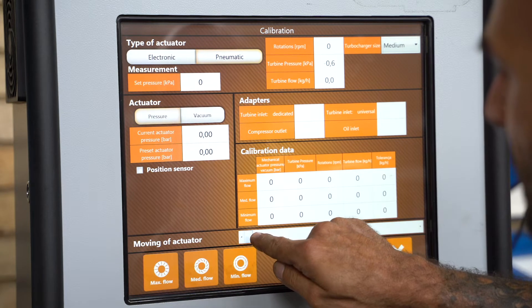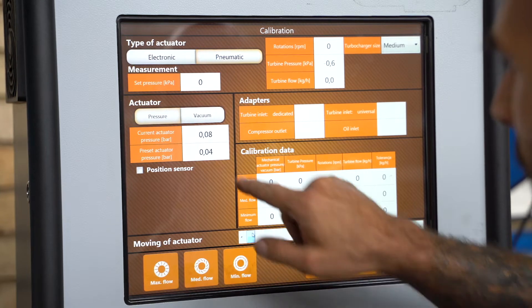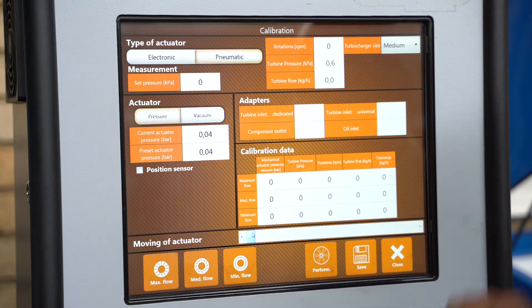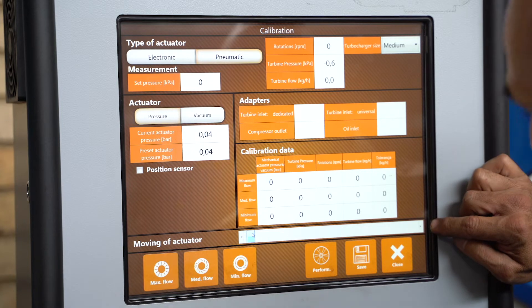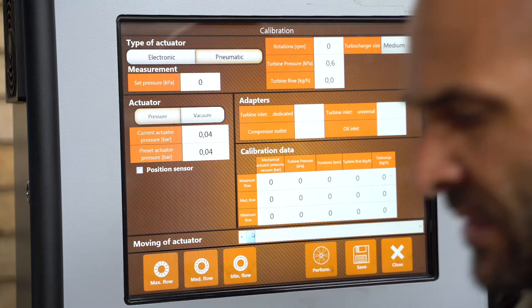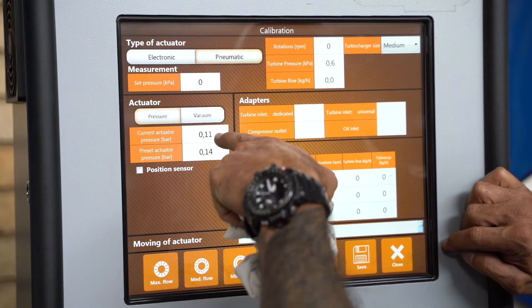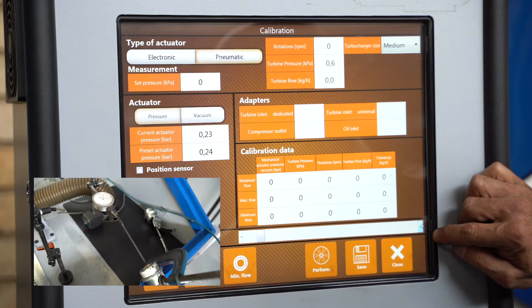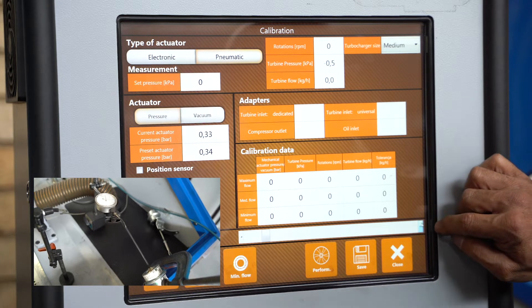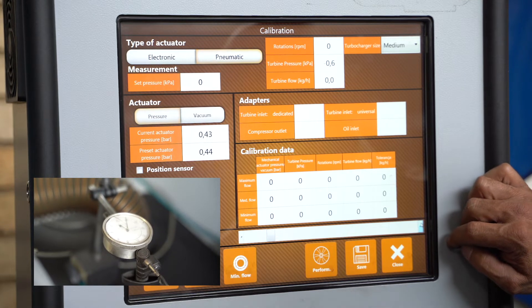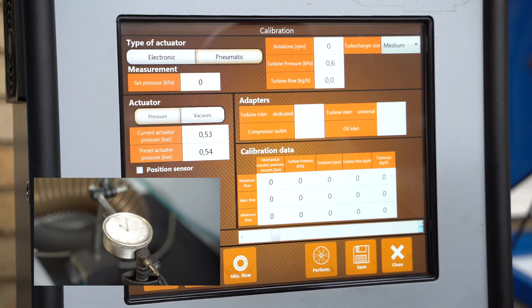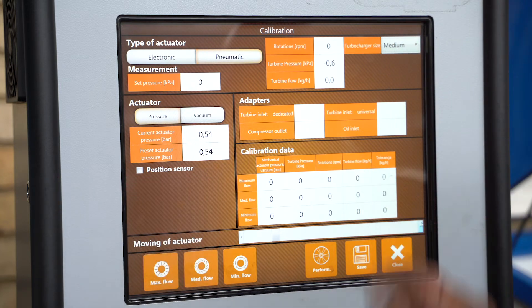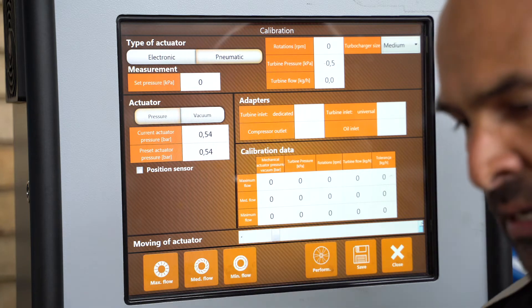You'll see on your screen the dial gauges there. I'm now incrementing up at 0.1 bar steps: 0.14, 0.24, 0.34 — actuator rod hasn't moved. 0.44 — still hasn't moved. 0.54 — as it climbs, see the dial gauge? It started to move. The rod has moved on the actual pin. At 0.54 of a bar, this specific actuator is cracking.